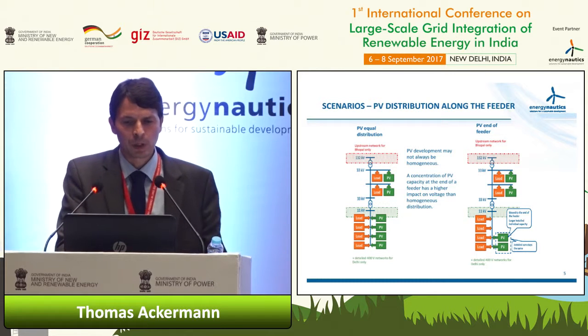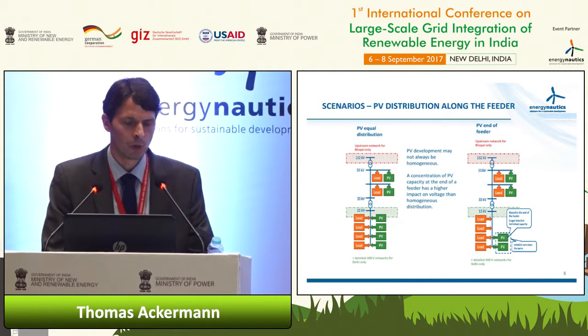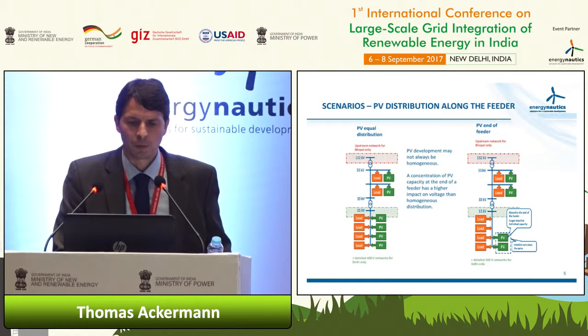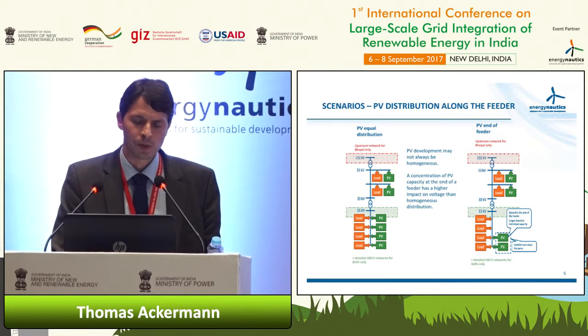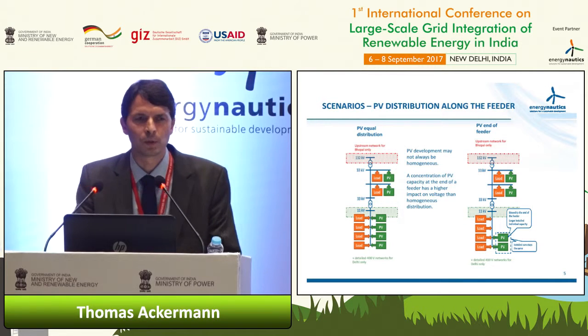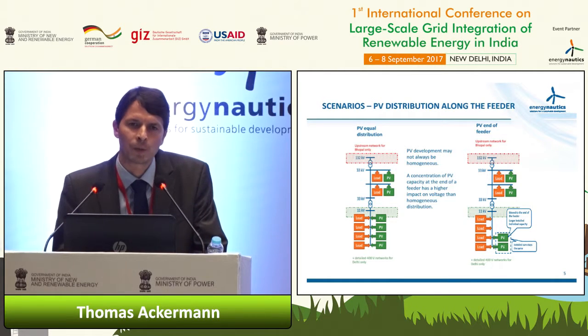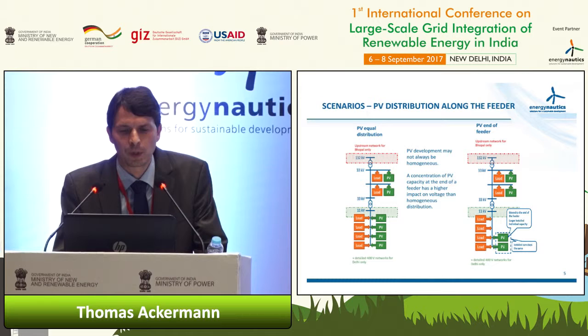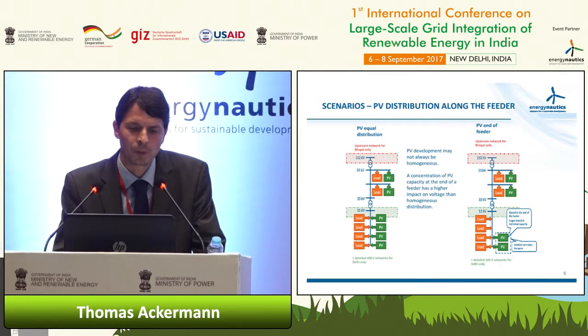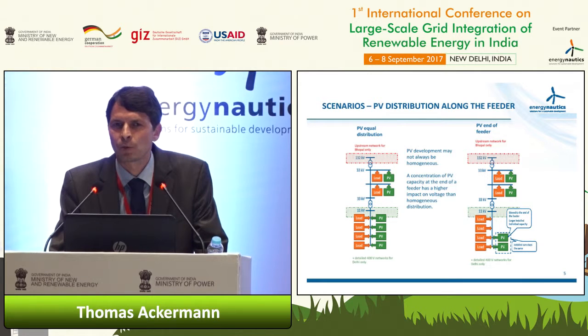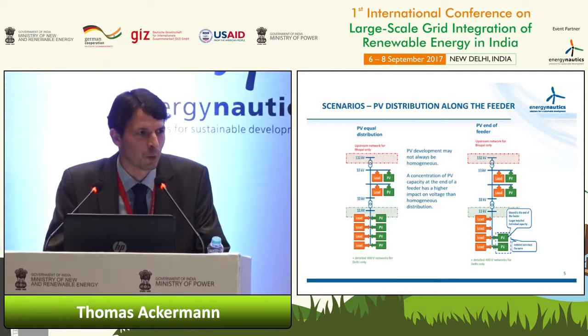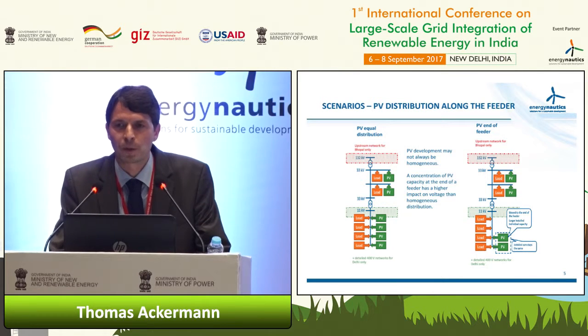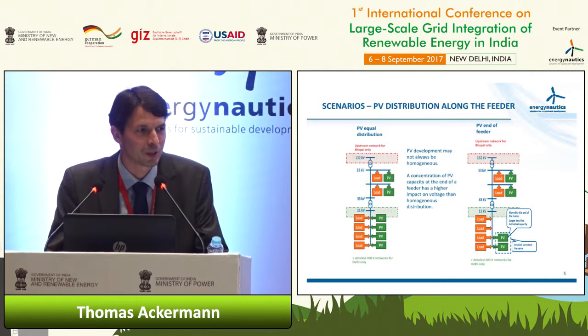The scenarios we looked into - I just wanted to show two of them. The first approach assumes that PV is distributed evenly in the system, in the 11 kV system, as you can see here. We rated it basically to the distribution transformer capacity. That's important to note, because when we talk about penetration rate, it's really important to mention what exactly you're rating it to.